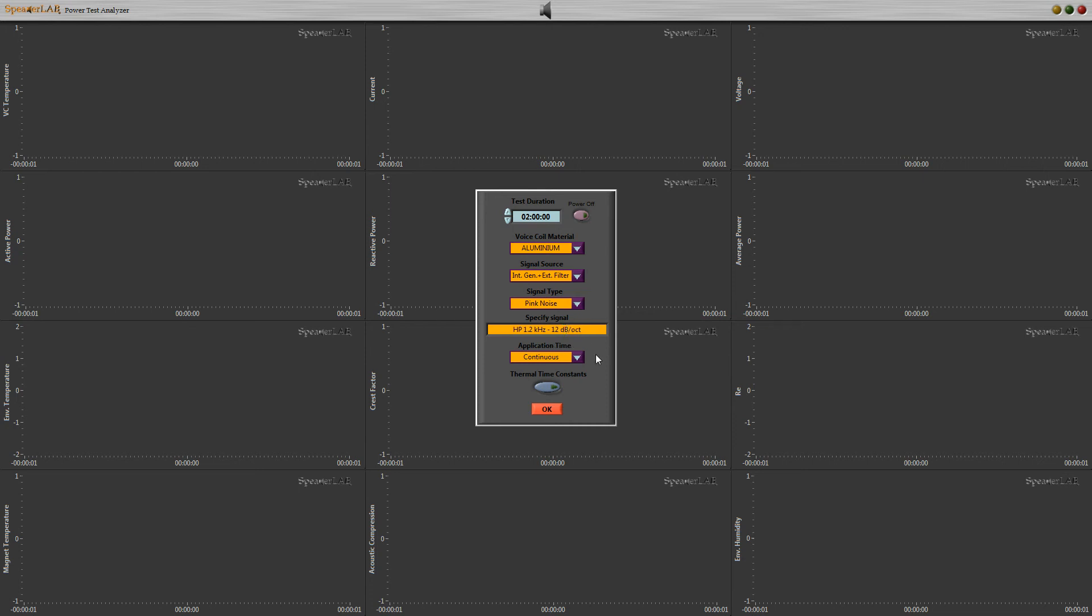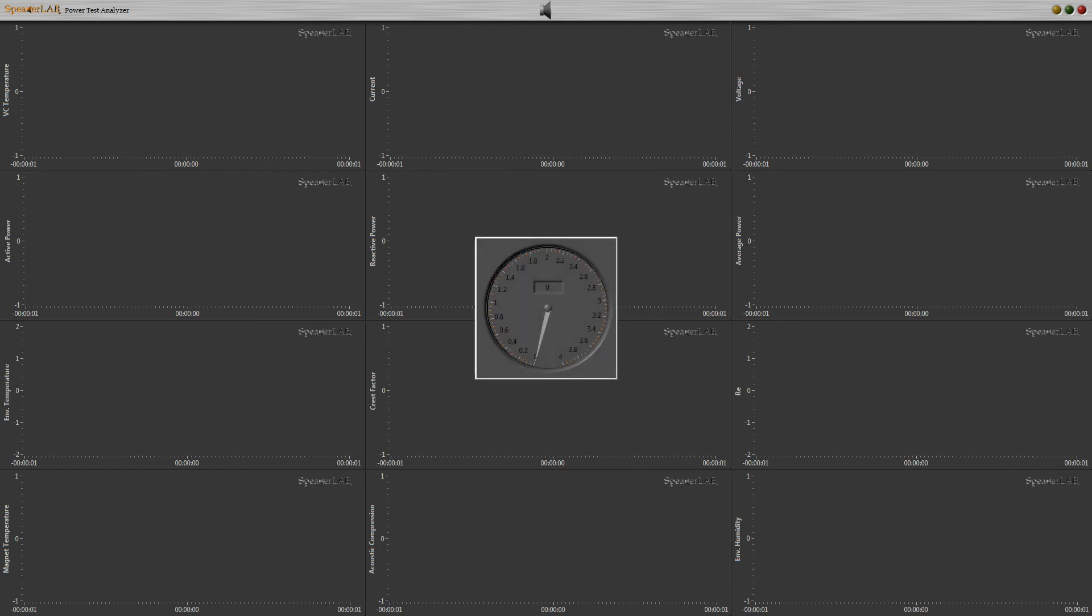Application time is continuous, duty cycle, or duty cycle with ramp. Now we select continuous test, excluding thermal time constants. Wait until the sequence completes all settings and measurements.